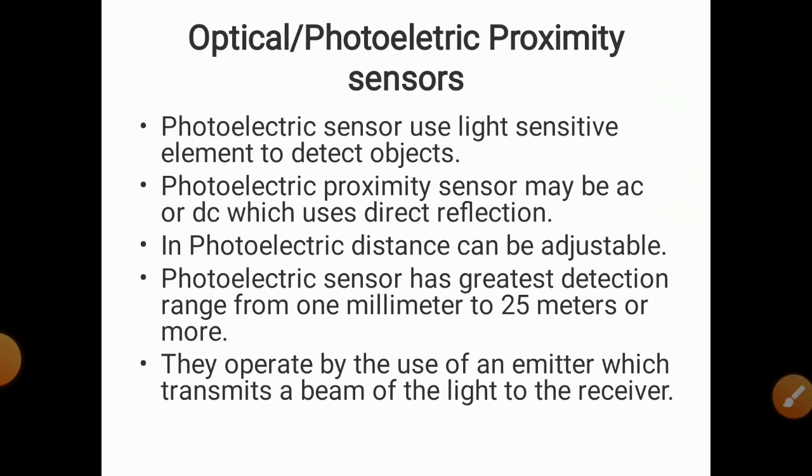We will now study the next type — the optical or photoelectric proximity sensor. The name suggests that we use a light-sensitive element to detect objects, using a light beam. The photoelectric proximity sensor may be AC or DC and uses direct reflection. The distance can be adjustable, and this type has the greatest detection range — from 1 mm to 25 meters or more.